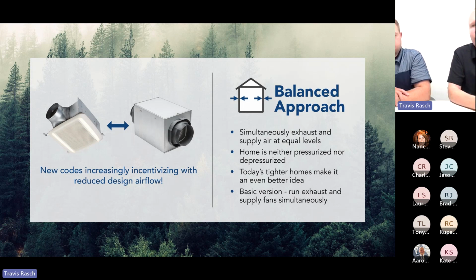The most simple way to do balanced ventilation is the image on the left here. Run a bath fan at 60 CFM, run a supply fan at 60 CFM. You're going to be balanced, which is great, but you won't get that great recovery benefit, recovering the difference in temperature and the difference in humidity.